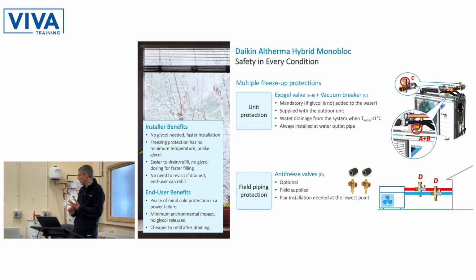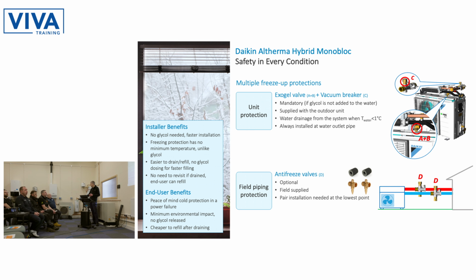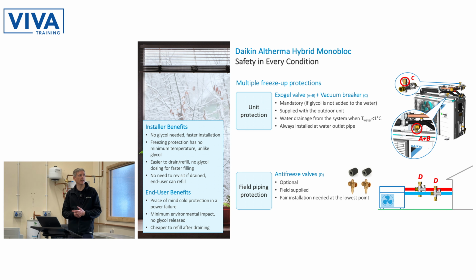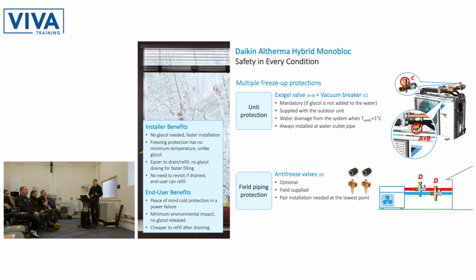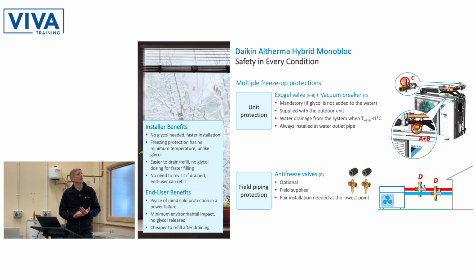So we've got an accessory that comes as standard. It's not fitted as standard, so it's quick and easy to put in, what we call an exogel valve, and that can actually drain down the water in the heat pump heat exchanger in that worst case scenario where the water's getting too cold and reaching the point of freezing. So that will drain down the heat exchanger to protect that. That's mandatory if you haven't got glycol in the system, and I'll come to that in a minute. If you have got antifreeze in the system, then you don't want to put that valve in. So when it thinks the water's getting down to sort of -1, it will drain that heat exchanger down. And that's installed on the water outlet pipe. There's a specific place for it to go on the heat pump.